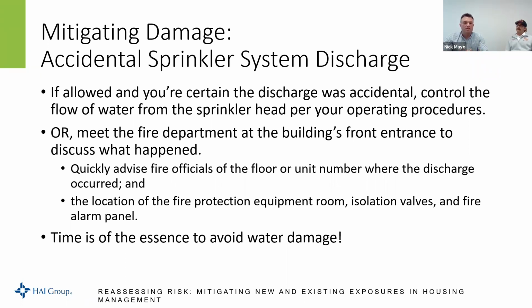So what are we saying here? Time is of the essence to avoid water damage. If that sprinkler head is flowing and you can't control it, as soon as the fire department gets there, if we know where we're going, then we can get there faster.